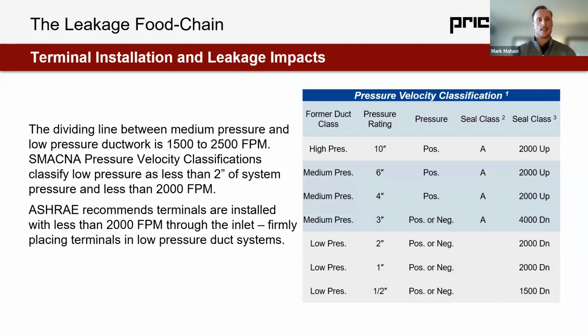So when we think about terminal installation or terminal leakage specifically, looking at the leakage food chain, this is, I guess, more affirmation of this being really low pressure class. The dividing line between medium pressure, which we really don't see in installs most of the time, and low pressure, when we look at ASHRAE and SMACNA, we're usually seeing somewhere between 1,500 and 2,500 feet per minute as the air velocity within ductwork that's going to define medium pressure to low pressure. Now, when we look at a terminal unit, terminal units are generally installed with at maximum 2,000 feet per minute through the terminal unit inlet. The reason for that is actually interesting. Primarily, it's because above 2,000 feet per minute, we're going to start to see generated noise. So air by itself, self-generating and creating more noise just from the air moving through ductwork. So we start with an acoustical rationale why we don't go above 2,000 feet per minute.